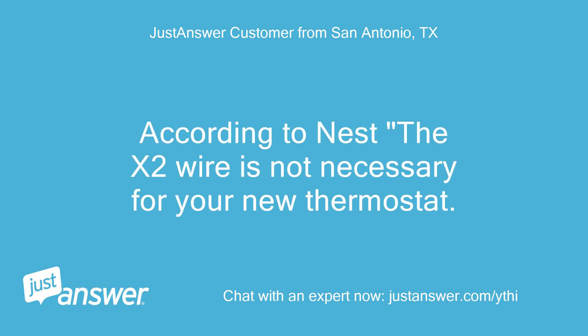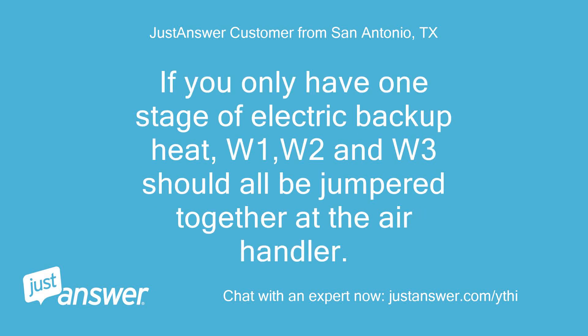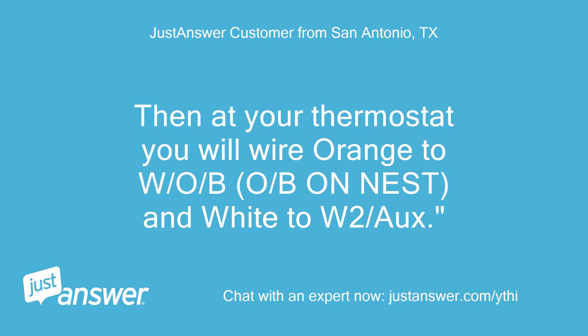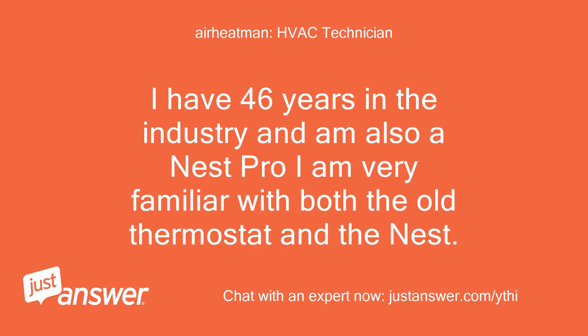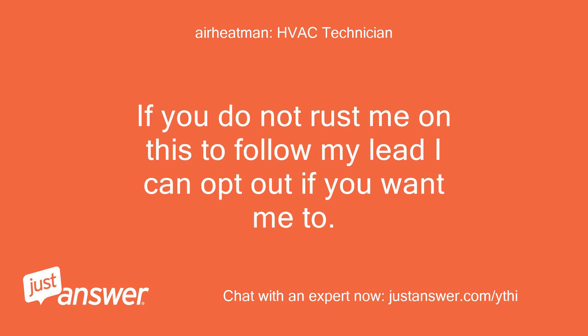According to Nest, the X2 wire is not necessary for your new thermostat. The wiring from the condenser X2 terminal should already be going to W3 on your air handler. If you only have one stage of electric backup heat, W1, W2, and W3 should all be jumpered together at the air handler. Then at your thermostat, wire orange to W/O/B (OB on Nest) and white to W2/Aux. I have 46 years in the industry and am a Nest Pro — familiar with both the old thermostat and the Nest. I have made a drawing and explained where each wire should go.